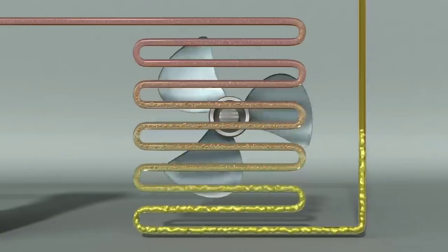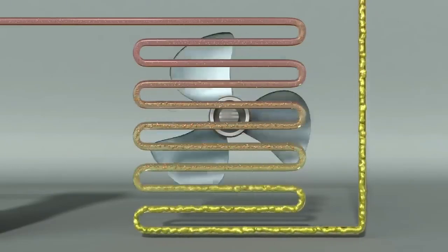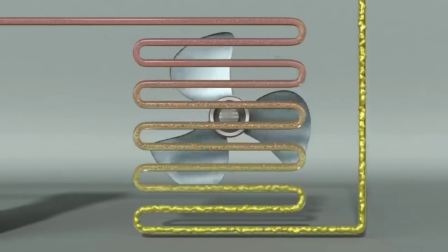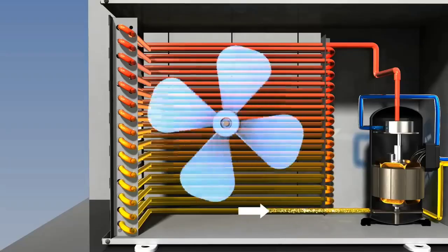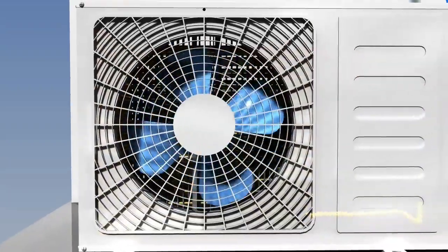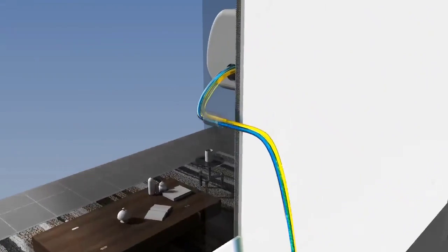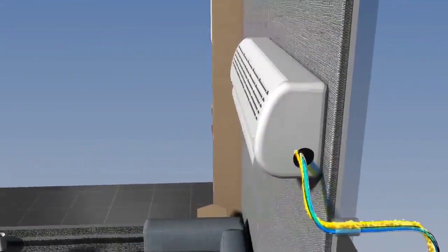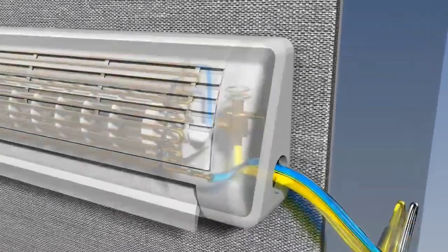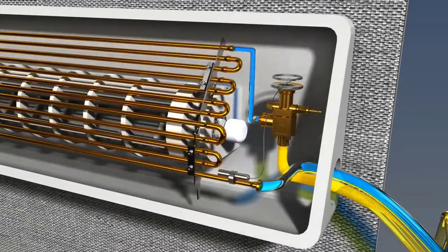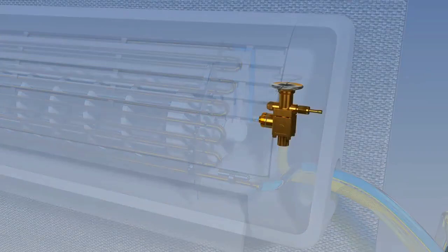A refrigerant in gas state of high temperature loses heat as it passes through a condenser. As such, it becomes condensed and at the exit, it turns into liquid almost. Although the refrigerant has thrown off some of the heat as it passes through a condenser, it is still hot, with temperature at about 50 Celsius. The refrigerant in high temperature and high pressure liquid flows into expansion valve.